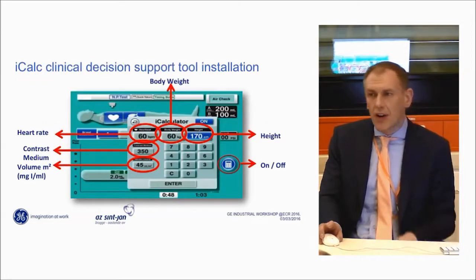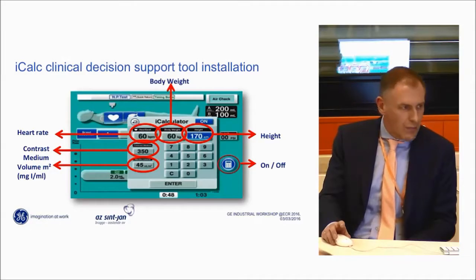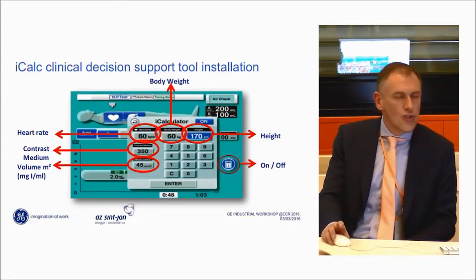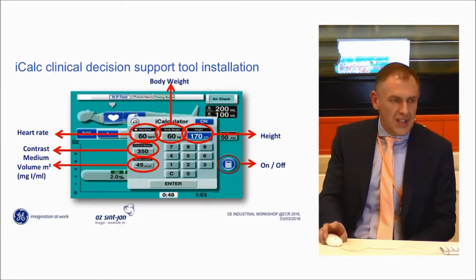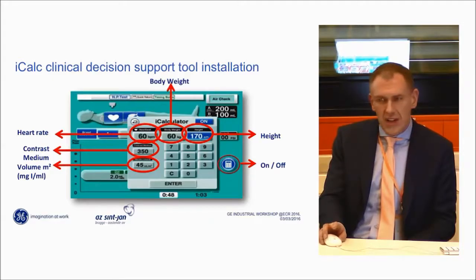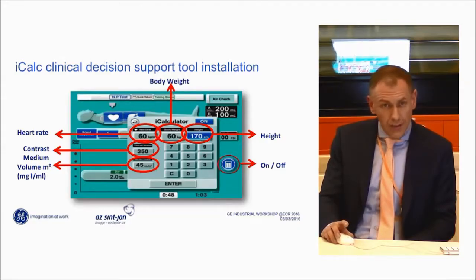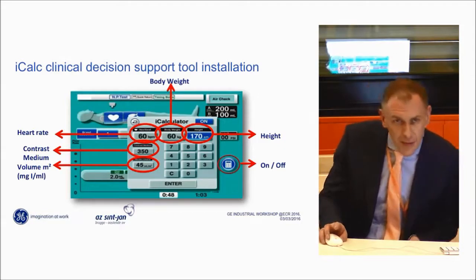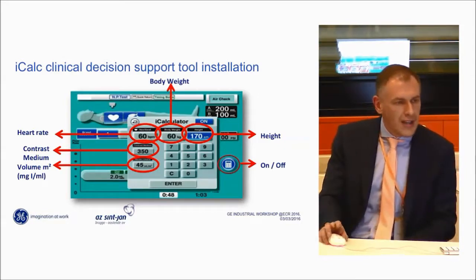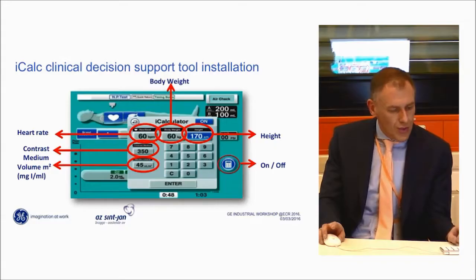We recently installed the iCalc system on our Nemoto injector. This is a clinical decision support tool that helps you calculate the volume you should inject for each patient. The interface is simple: you fill in the patient's height, body weight, heart rate, and the contrast medium being used. Then, with the rule that you need 45 ml per square meter of body surface area, iCalc proposes a volume of contrast to inject.